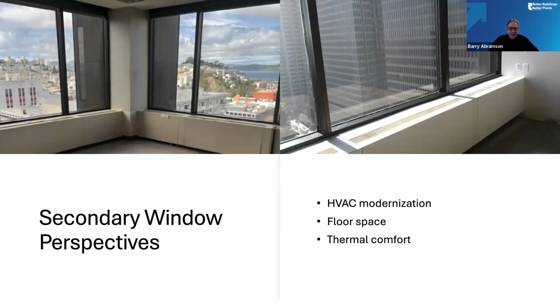That's exactly the case here: calculations showed heat load savings, and we can get rid of the perimeter induction system with perimeter heat once a good secondary window system is installed. That frees up floor space, which probably trumps any economic aspect of the project. Another benefit was thermal comfort, since there are a lot of challenges in this building from solar load and varying facades, so that was a big consideration too.